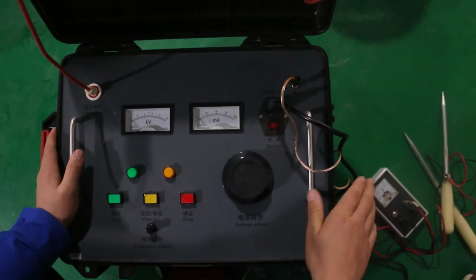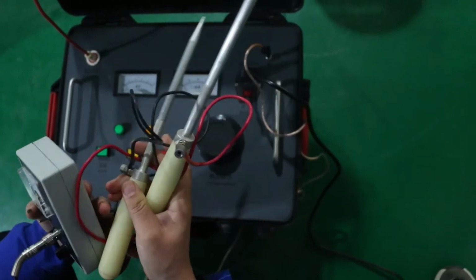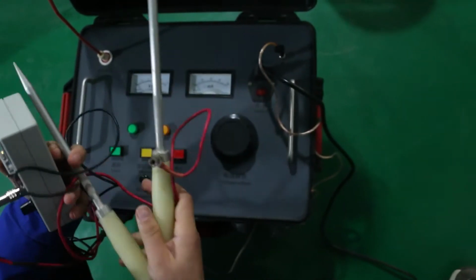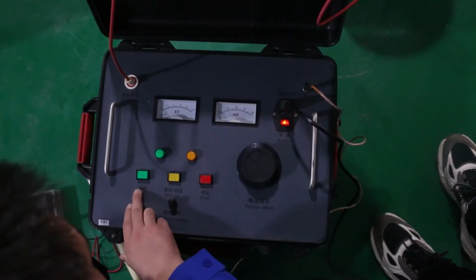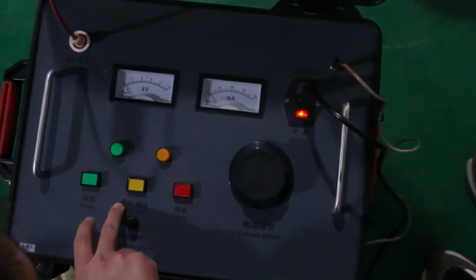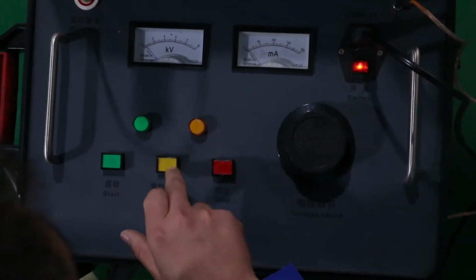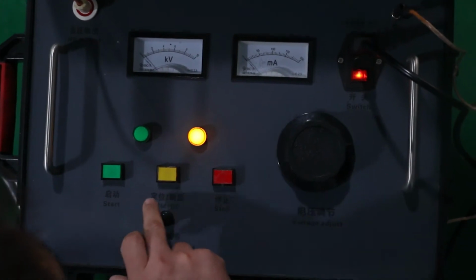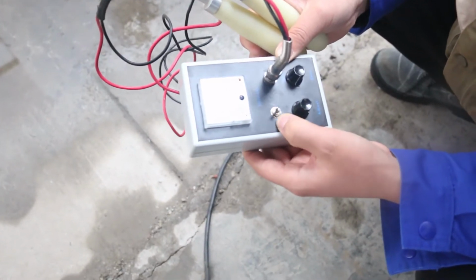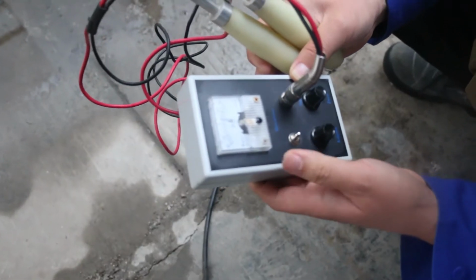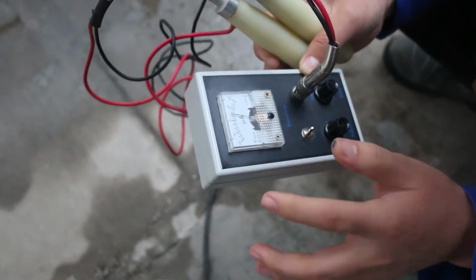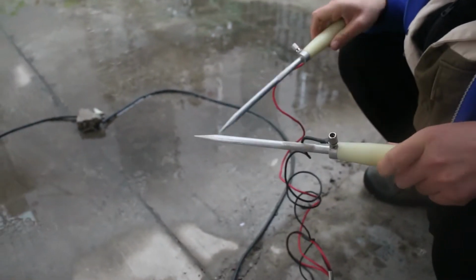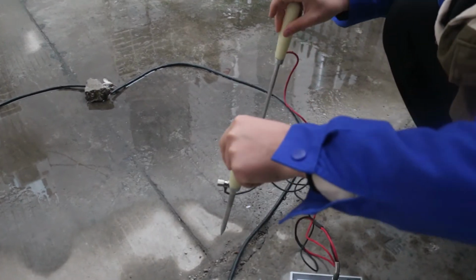XHHD523 is a cable sheath fault pointing instrument. The device is used to find a fixed point after the approximate location. It is actually a high-voltage pulse source, which sends a pulse signal to the faulty cable. The pulse voltage is converted into current, and the step voltage method is used to sense the direction of the current through the receiving box and the ground rod to find out the specific fault point.